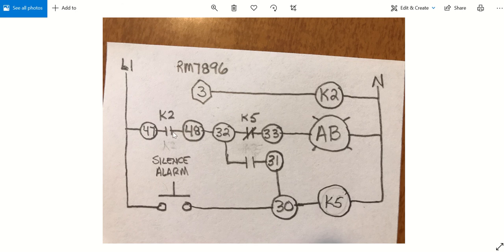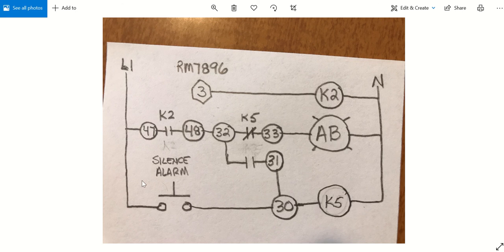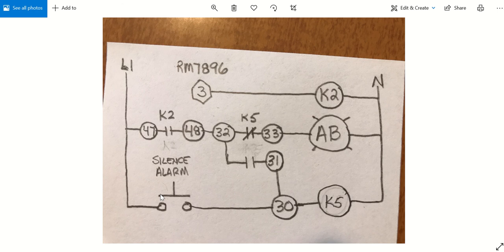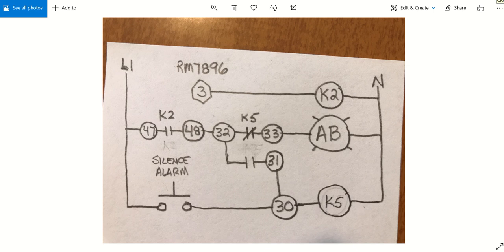When you look at this, K2 and the silence relay are kind of in parallel with each other, along with this normally open contact of K5. That's what gives you that latching circuit so that when you press the silence button, it will energize K5 and silence the alarm bell because this contact goes open. But it will close this contact. We have a parallel path to keep K5 energized, which means that you can release the silence button. That's relay logic 101 kind of stuff that everybody should know. I will ask some questions about that.